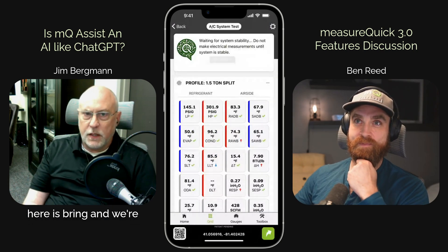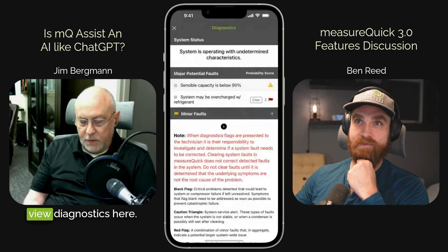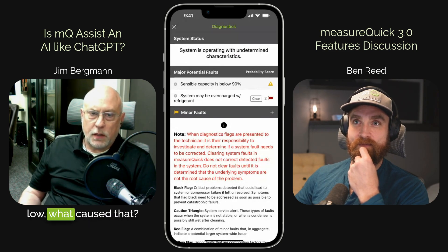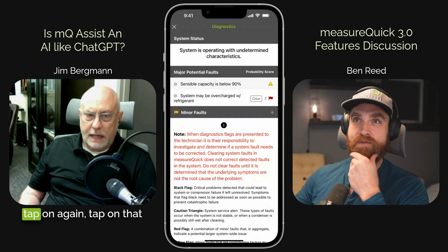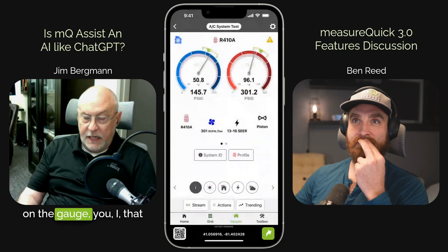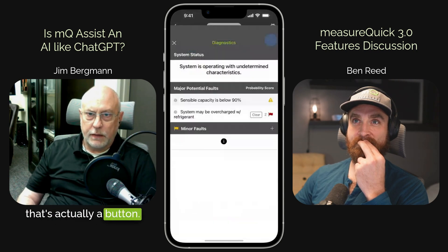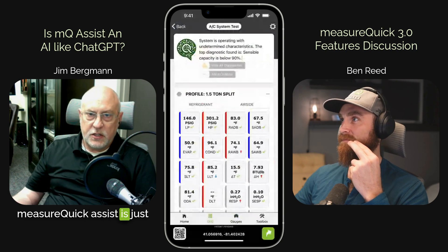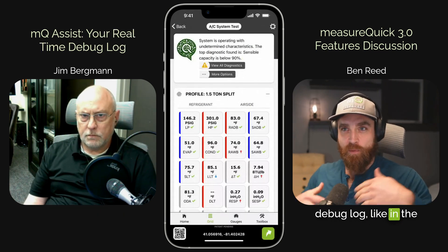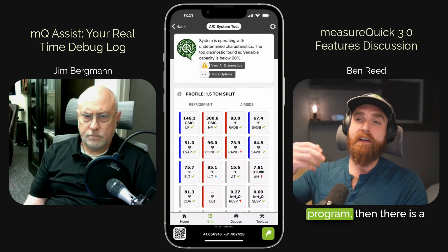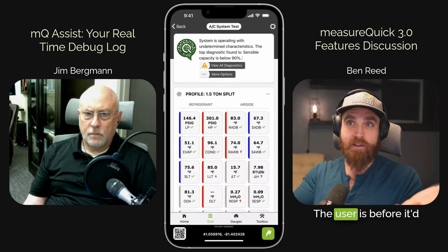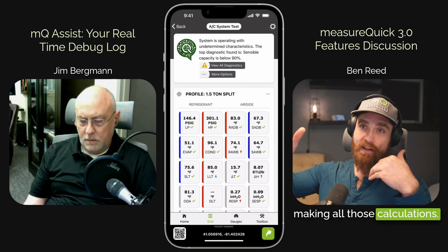What it's trying to do here is bring things forward. We'll click on the view diagnostics here. What it's doing is pulling that data up to the front so we can actually see what's going on — whether sensible capacity is low, what caused that, or whether refrigerant charge is overcharged. We can tap on that and see what's going on with that specific fault. It allows us to just bring some things forward. In the gauge UI, that same information is there, but it may not be apparent it's actually a button until you tap it. So that grid view and MQ Assist is just designed to be a tool that makes sure you get to the right sections of the app. It seems like a debug log — like in the world of computers there's a terminal spitting out context — and now you've provided that to the user. Before, all those calculations were happening in the background, but now it's showing: here's a context change, make sure you know this is happening.